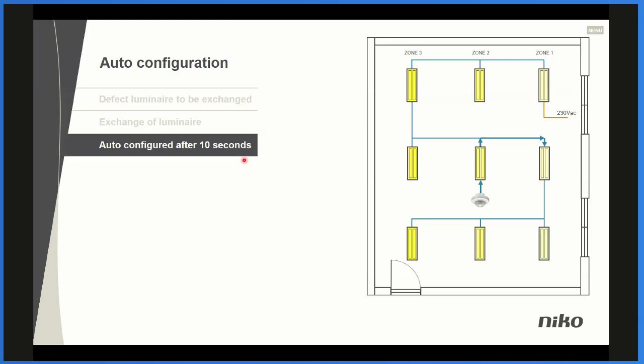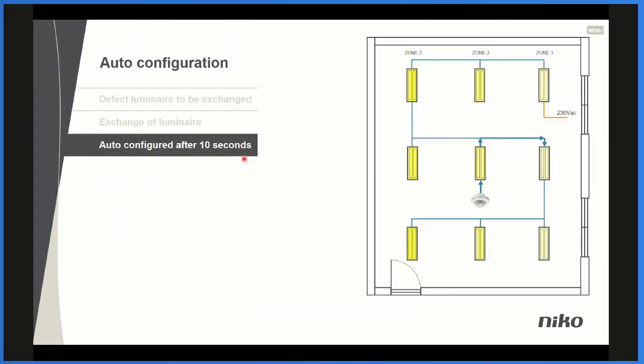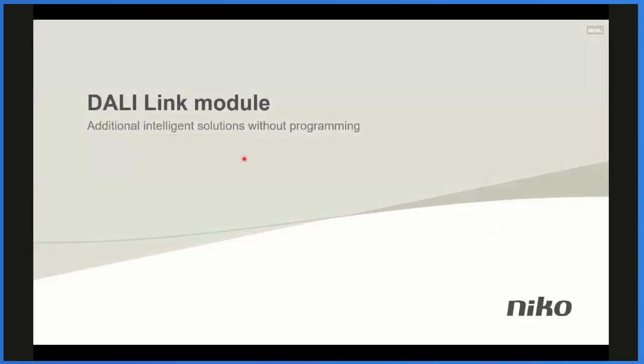As I said, with the DALI installation, there's one power supply in each and every DALI installation. But sometimes it is necessary to communicate between two DALI buses. That means if you have two master detectors, you would like them to cooperate together. And we can't do that just with wiring. We have to have a device between, and this device is a link module. That means it's a module that can link one or more DALI buses together with more power supplies.